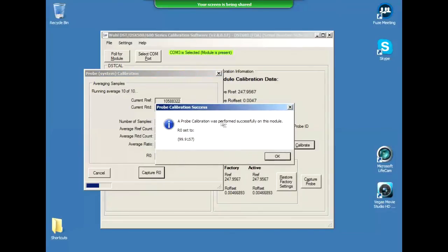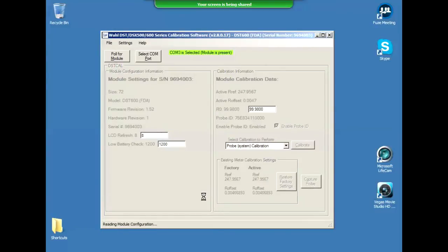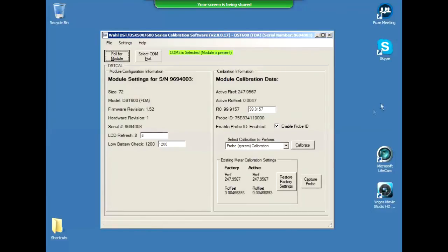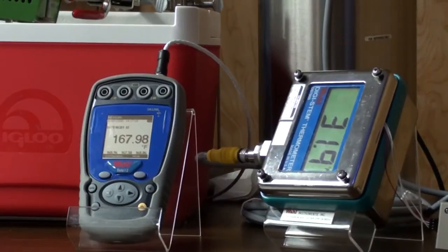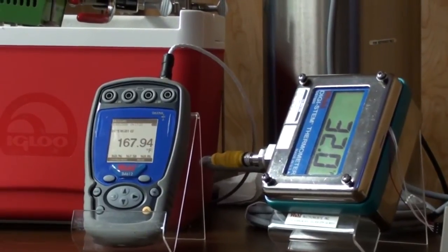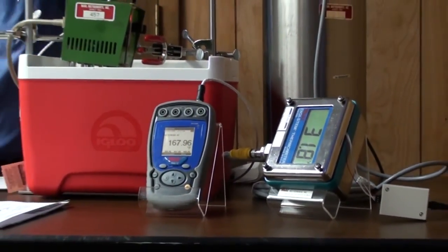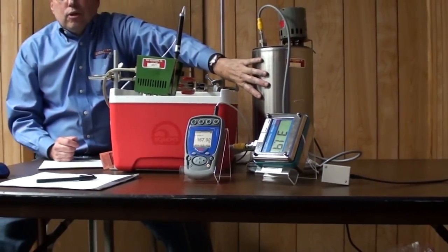And it says it's performed it. So we're going to say okay. Now this part takes a few seconds for it to do, and I'm going to turn this off while it's doing that. Now what it's doing is communicating over that serial link to this device. And now you can see that R0 has been populated with 99.9157. So what we just did was we used the DST600 meter as an ohm meter to measure the resistance of this probe in an ice bath at 0 degrees C.